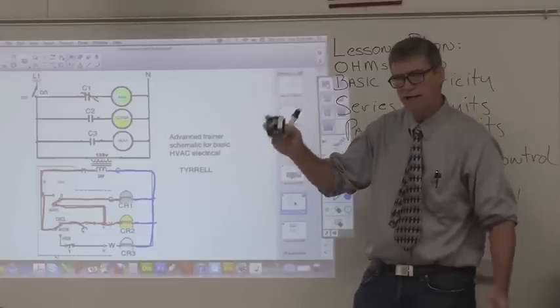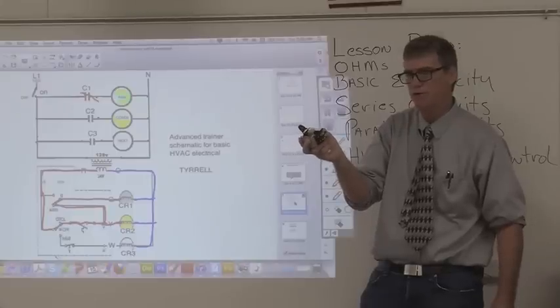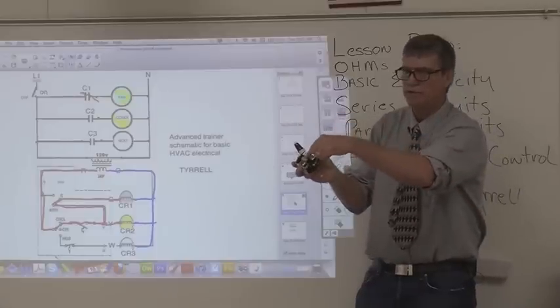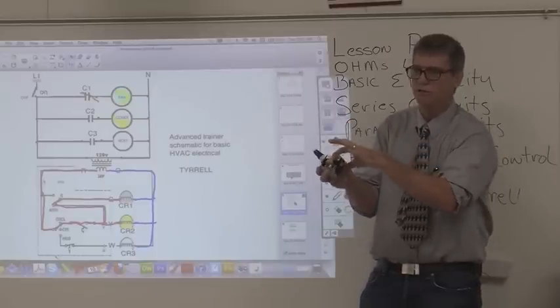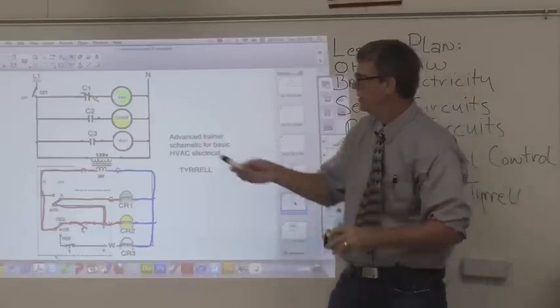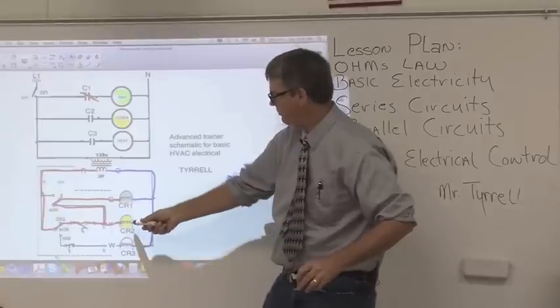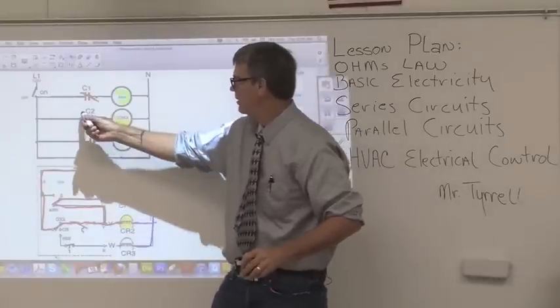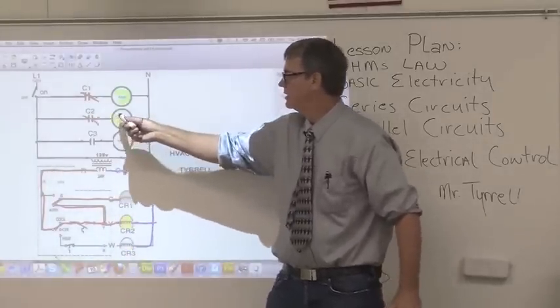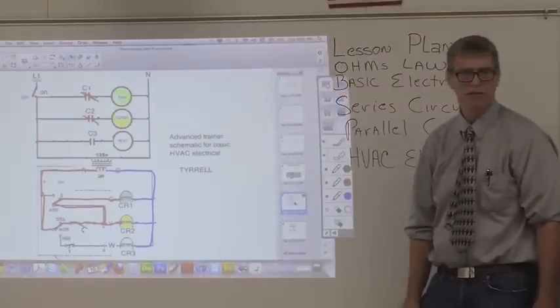This was called a contactor because the contacts are bigger, but a relay can have smaller contacts because that fan motor is not going to draw a lot of amperage. When G hits that coil, it's going to suck it closed. It's going to close C1. When we sent power out Y, we closed C2. This power went out to the condenser; this power went to the fan.